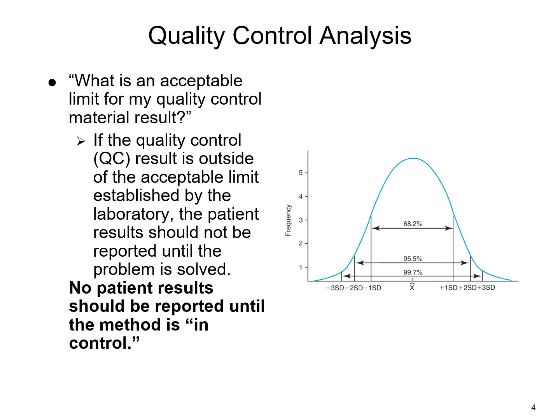So you do have to follow the CLIA regulations and the various standards that are set within your laboratory, as well as the manufacturer of the analyzer or the particular test or analyte that you're looking at. You've got to follow those directions for how often to do QC. But we're looking for those results to fall within those standard deviations, and we use those Westgard rules to determine if QC is acceptable.